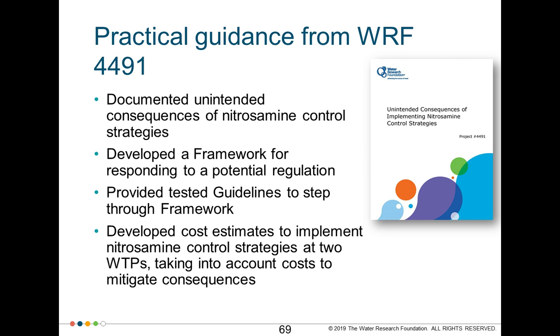Another question: what is Uniform Formation Conditions, or UFC, and what is the difference between UFC versus simulated distribution system, SDS, versus Formation Potential, FP? Uniform Formation Conditions were developed as a procedure for trihalomethanes — Scott Summers authored a paper establishing a uniform approach to look at DBP formation at levels more relevant to where utilities typically disinfect. In contrast, Formation Potential adds a lot of chloramines and reacts for a long time to try to react all the precursors that are reactable in a sample. Simulated Distribution System conditions are yet another approach where you chloraminate under site-specific conditions.